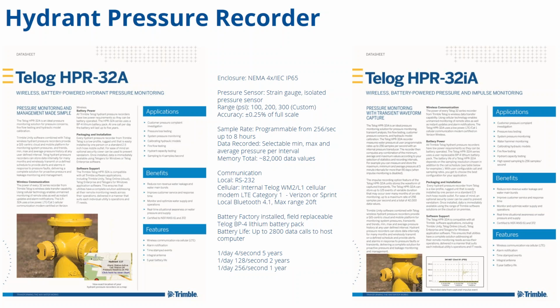So where the HPR 32A can sample around 1 time per second, the HPR 32IA can sample up to 256 times per second. And the reason that we have this high rate of data capture is the IA is made for capturing water hammers. And water hammers and other impulse or transient events happen within a split second of time. So the electronics in the pressure sensor built into the 32IA is much more sensitive when we're able to capture that information. So depending on the application that you're trying to use, we have a product for you.